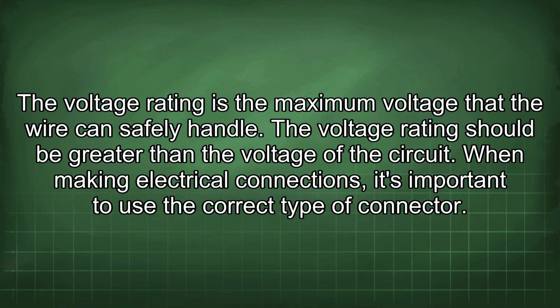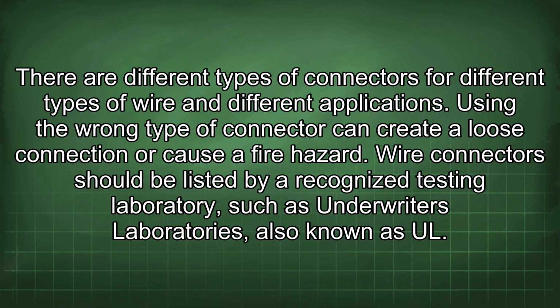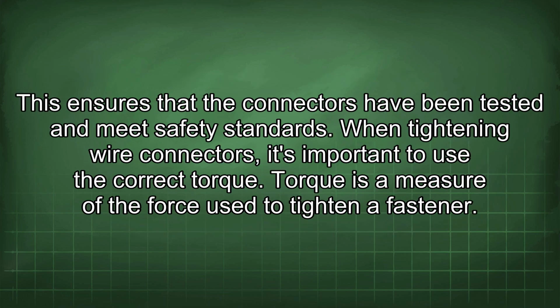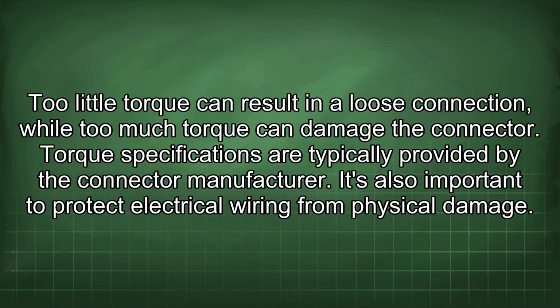When making electrical connections, it's important to use the correct type of connector. There are different types of connectors for different types of wire and different applications. Using the wrong type of connector can create a loose connection or cause a fire hazard. Wire connectors should be listed by a recognized testing laboratory, such as Underwriters Laboratories, also known as UL. This ensures that the connectors have been tested and meet safety standards. When tightening wire connectors, it's important to use the correct torque. Torque is a measure of the force used to tighten a fastener. Too little torque can result in a loose connection, while too much torque can damage the connector. Torque specifications are typically provided by the connector manufacturer.